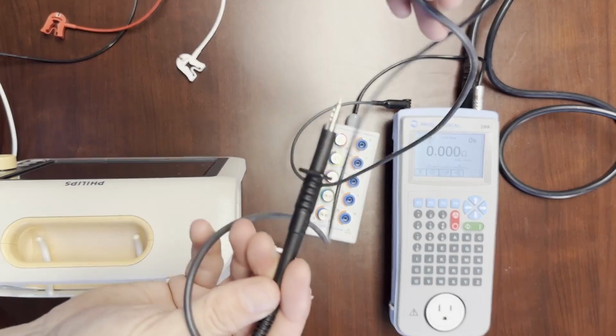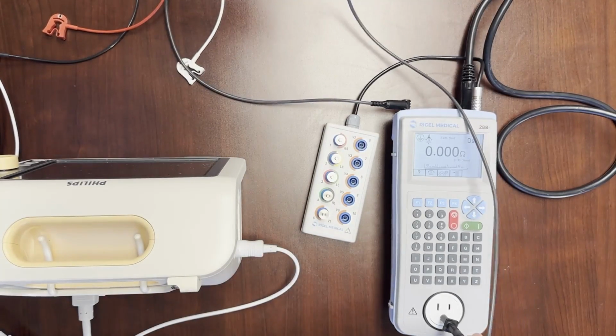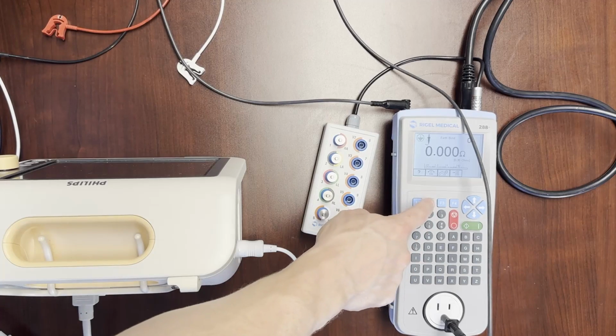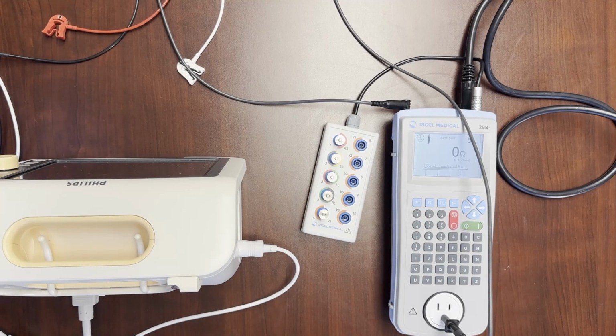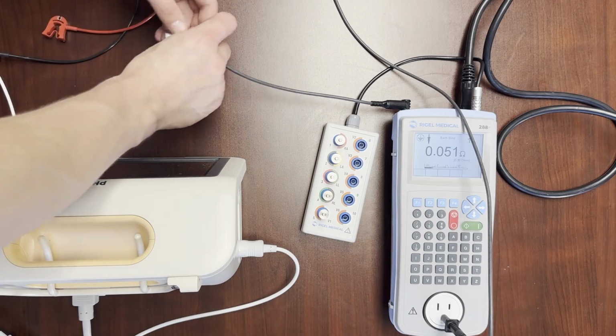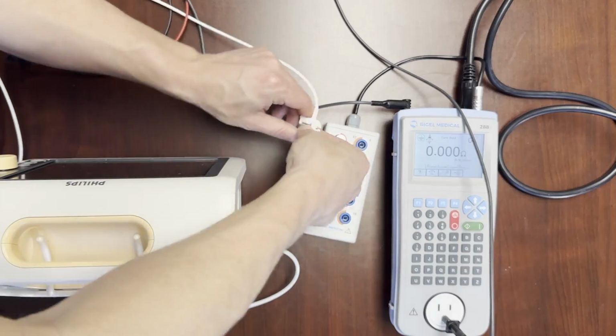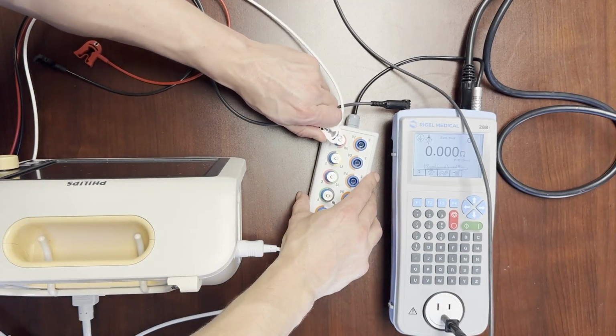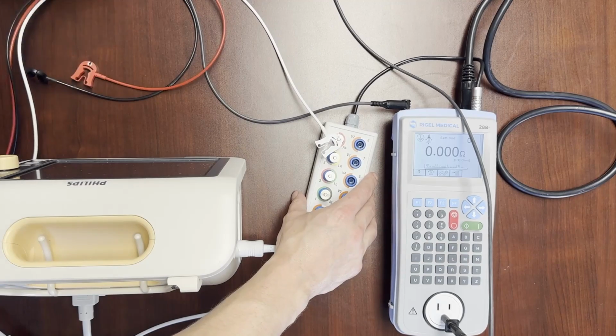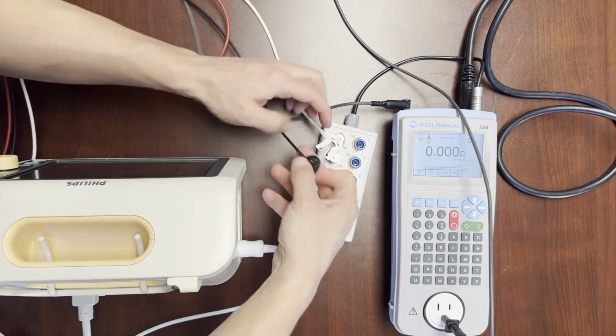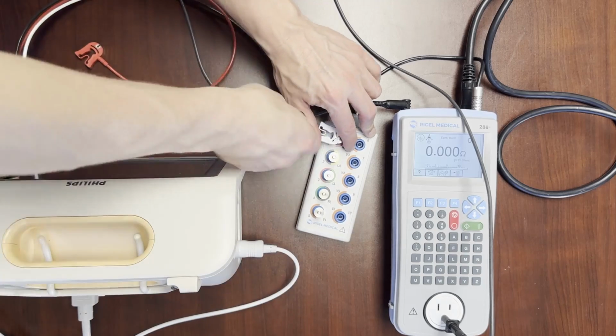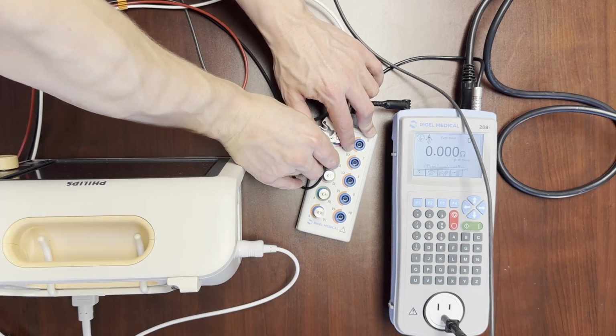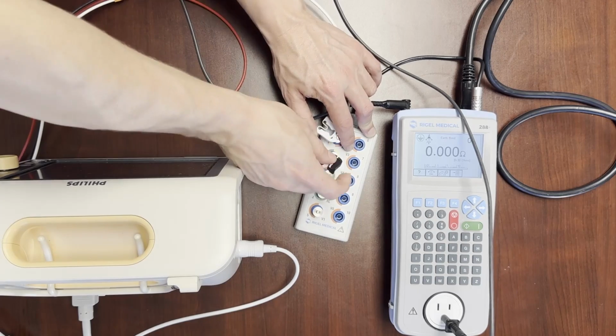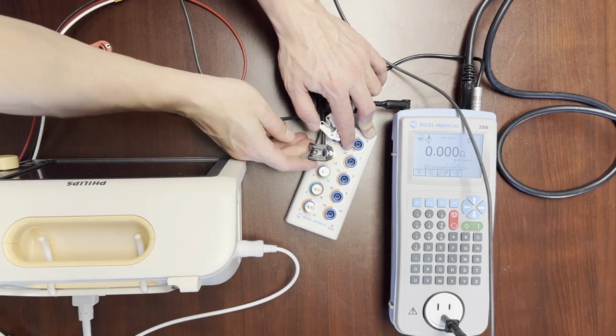So we connect up the device in the same way that we do with the SafeTest 99. It's the same connection, so firstly we need to zero out those leads that we've got connected to the rear of the 288 safety analyzer, and then we can connect that to the rear of the analyzer. While that's zeroing out, I'll just connect up these patient lead connections to the ECG snap adapters, and then after this I'll plug in the earth bond lead to the rear of the analyzer, much like we did with the SafeTest 99.